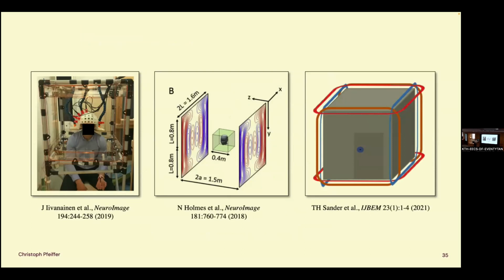So what we have to do is improve the shielding otherwise in an existing room. One way to do that is a type of active shielding. You have coils that generate specific components of the magnetic field. Typically, you have 3 homogeneous components and then some first order gradients. You measure the magnetic field that is there and then apply a current to the coils that creates an opposite field, basically just cancelling it out.